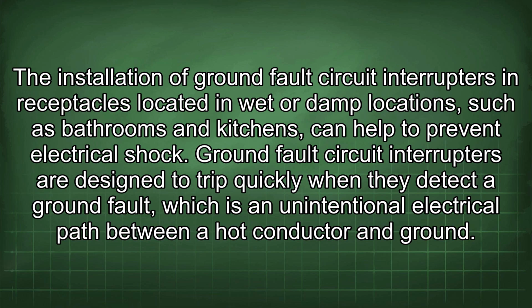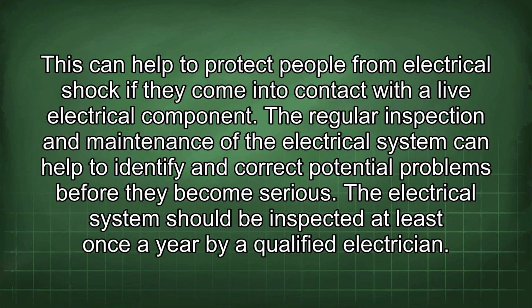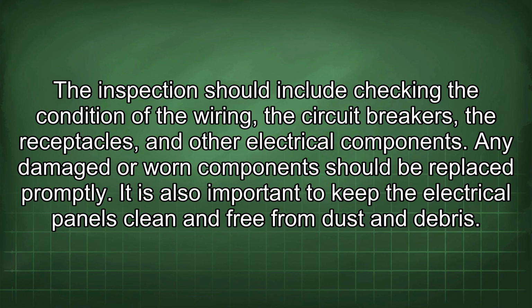Ground fault circuit interrupters are designed to trip quickly when they detect a ground fault, which is an unintentional electrical path between a hot conductor and ground. This can help to protect people from electrical shock if they come into contact with a live electrical component. The regular inspection and maintenance of the electrical system can help to identify and correct potential problems before they become serious. The electrical system should be inspected at least once a year by a qualified electrician. The inspection should include checking the condition of the wiring, the circuit breakers, the receptacles, and other electrical components. Any damaged or worn component should be replaced promptly.